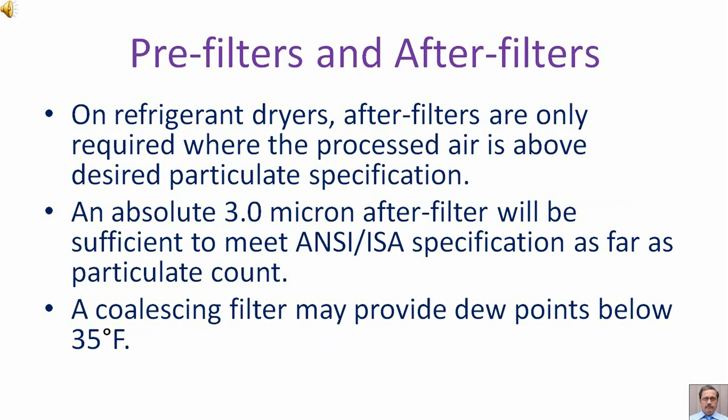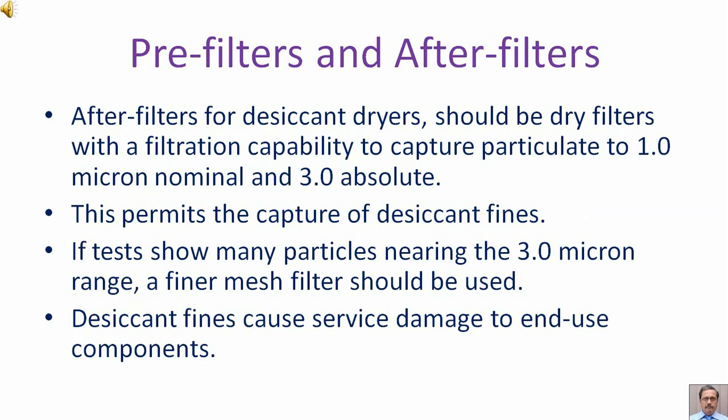On refrigerant dryers, after-filters are only required where the processed air is above the desired particulate specification. An absolute 3 micron after-filter will be sufficient to meet ANSI/ISA specifications as far as particulate count. A coalescing filter may provide dew points below 35°F.